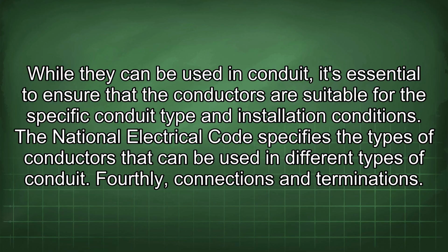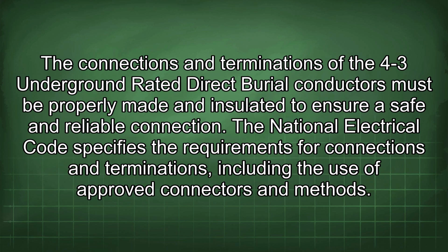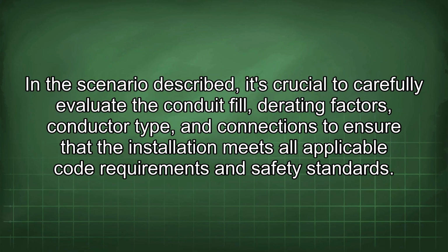Fourthly, connections and terminations. The connections and terminations of the 4-3 underground rated direct burial conductors must be properly made and insulated to ensure a safe and reliable connection. The National Electrical Code specifies the requirements for connections and terminations, including the use of approved connectors and methods. In the scenario described, it's crucial to carefully evaluate the conduit fill, derating factors, conductor type, and connections to ensure that the installation meets all applicable code requirements and safety standards.